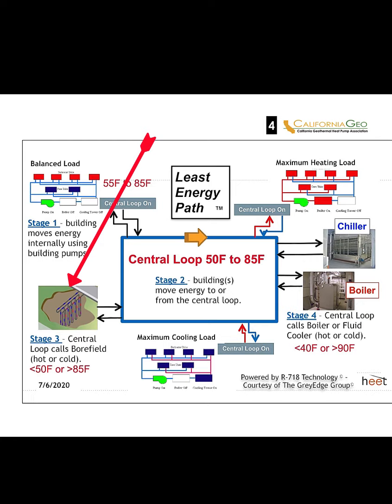Stage 3 represents activation of the geobore field to either warm or cool the central loop to remain within its limits. When the bore field cannot maintain those limits, the system employs Stage 4 as either a small chiller or boiler to correct it. Since 90% of a building's HVAC runtime is at 50% or less of maximum load, chiller and boiler use will be rare.